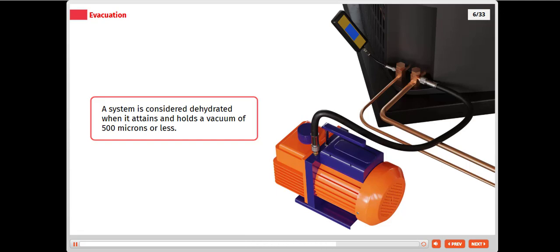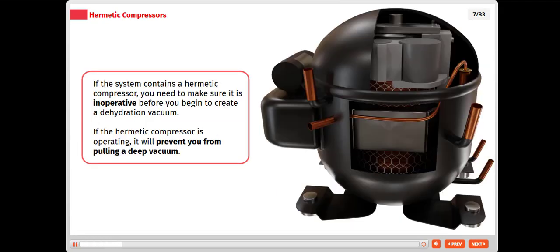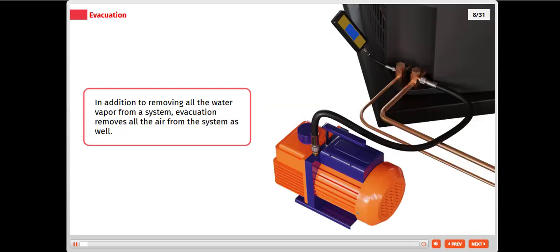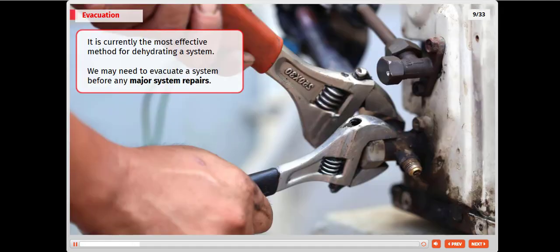If the system contains a hermetic compressor, you need to make sure it is inoperative before you begin to create a dehydration vacuum. If the hermetic compressor is operating, it will prevent you from pulling a deep vacuum. In addition to removing all the water vapor from a system, evacuation removes all the air from the system as well. It is currently the most effective method for dehydrating a system. We may need to evacuate a system before any major system repairs.